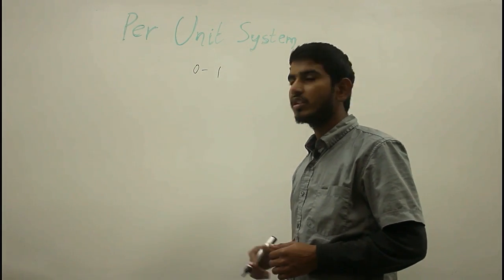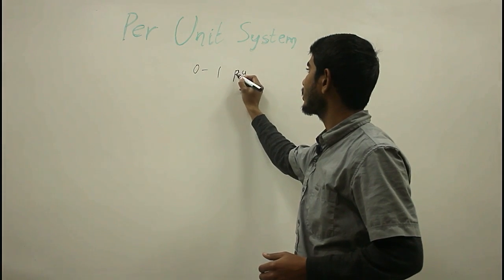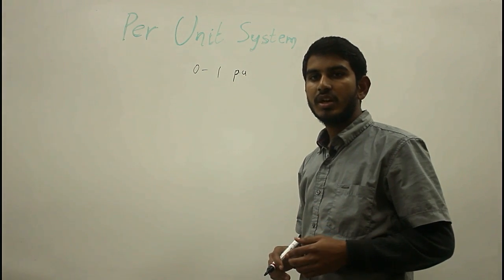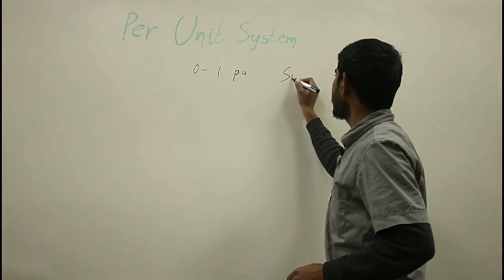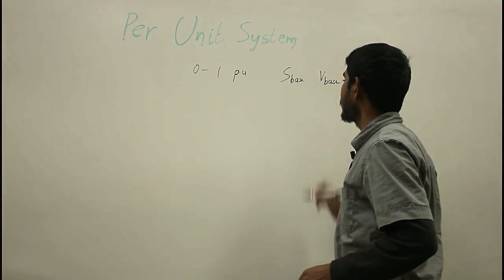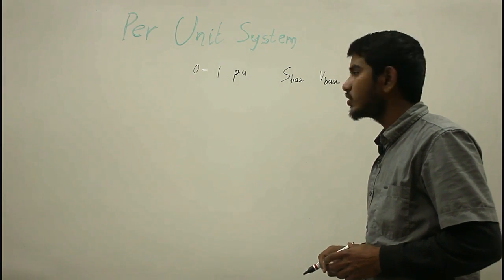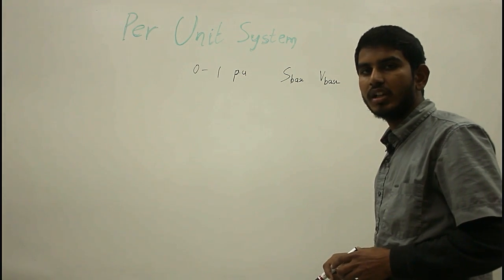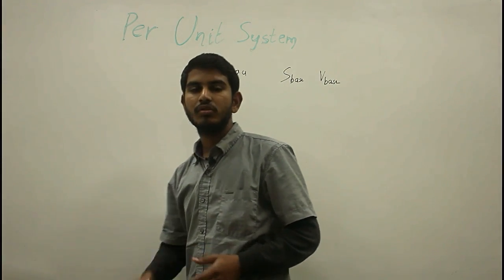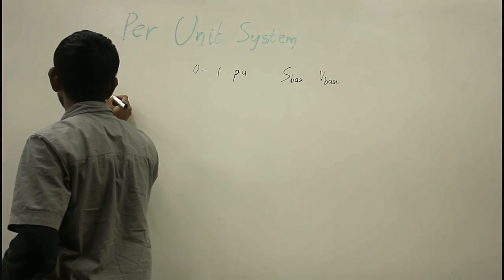Per-unit values are expressed as 'p.u.' — that is, per unit. Whenever you look at any machine, two base quantities are provided on the nameplate: power base and voltage base. By knowing these two base quantities, you can automatically determine the other two base quantities: current base and impedance base. The per-unit value is the ratio of the actual quantity to the base quantity.